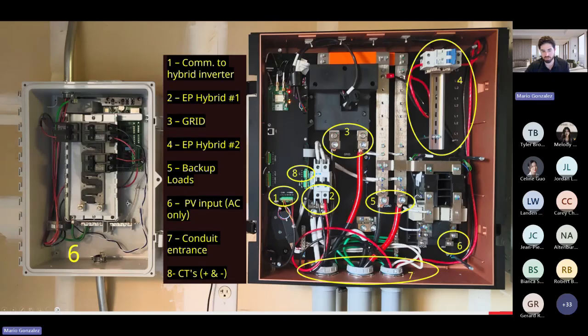And number 7, basically the conduit entrance, as you can see there. Very important. Make sure you don't have the DC coming in at the same conduit as the communication wires. AC doesn't matter because the wire is shielded. If it's not shielded, you have to run its own chase for the wire. And number 8, the CTs. Basically, you can hook up the CTs into this board over here.